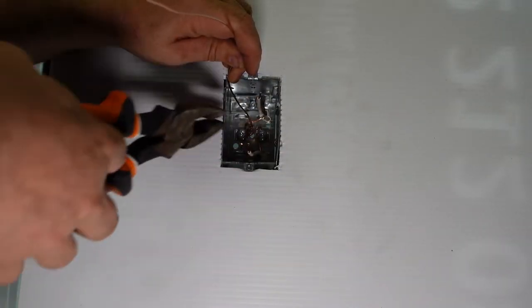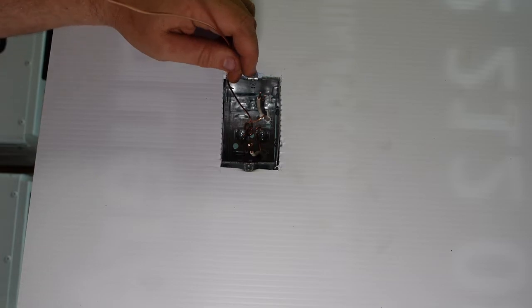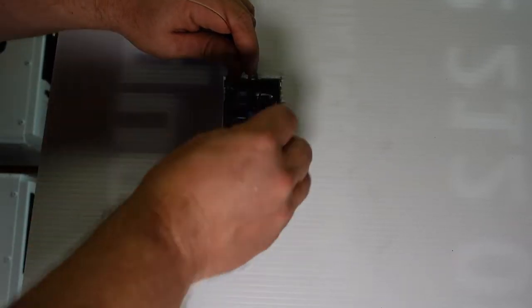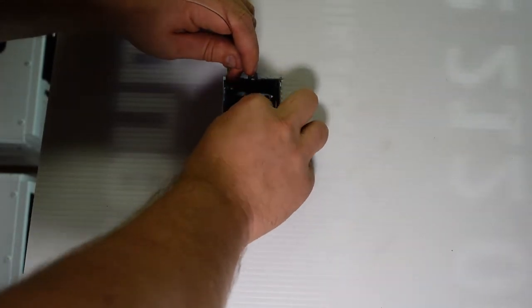Now additionally, we can always wrap it to the back of the box as well, but where the two are already done that way, I'm not going to bother. So to secure that connection, we're just going to go ahead and stick a wire nut on the back of it. And where it's so short and I can't really get my fingers in there, I'm going to take my linesman's and give it an extra twist. A couple twists maybe. And then we're going to stick that right into the back of the box there. There we go. And that gives us a ground wire.